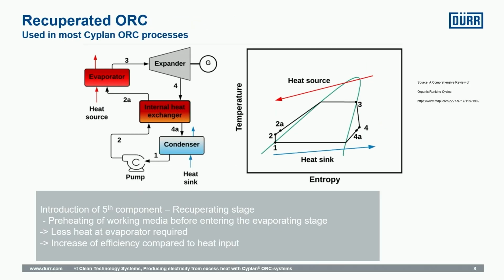And one step further to enhance the efficiency, more often there's another heat exchanger in between, which is just an internal heat exchange between the steam that has not yet been condensed, and the other liquid, the ORC working media, before it's sent to the evaporator.